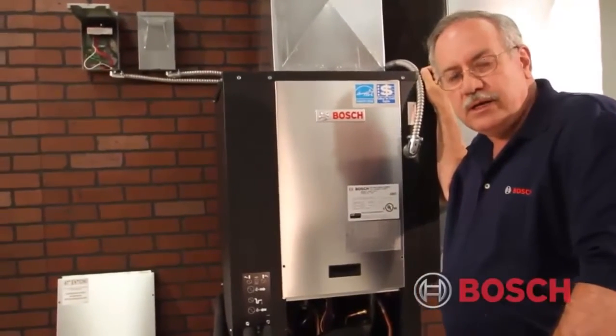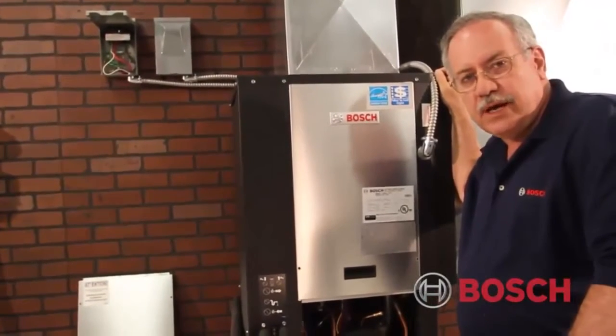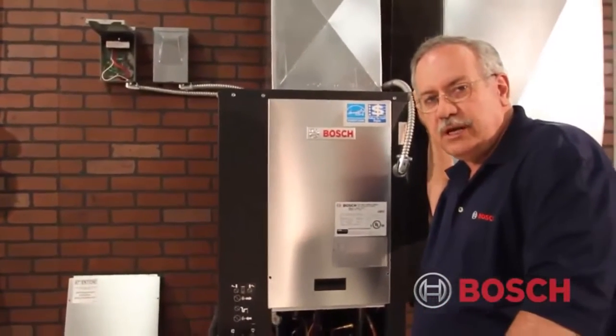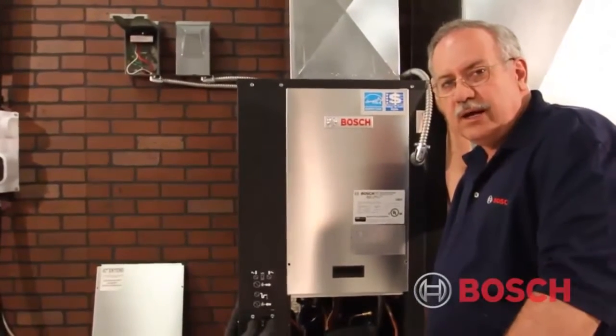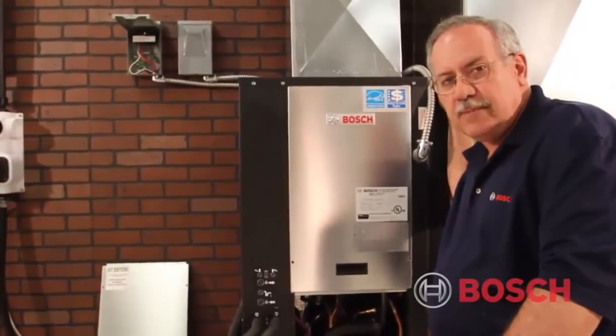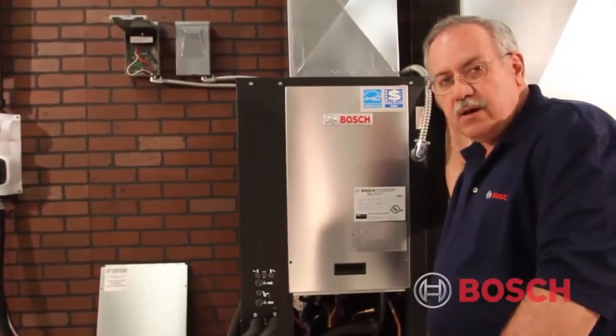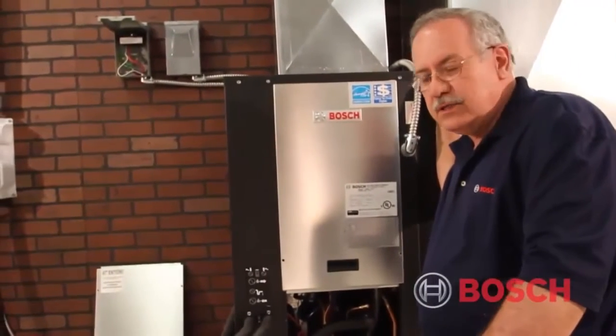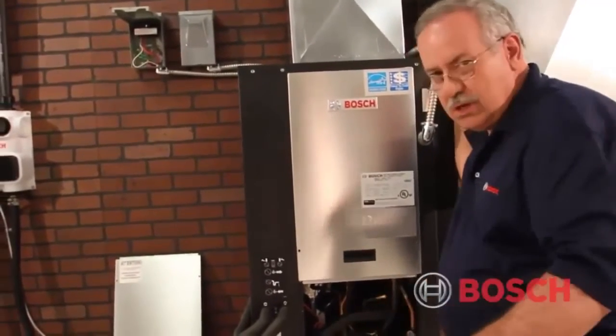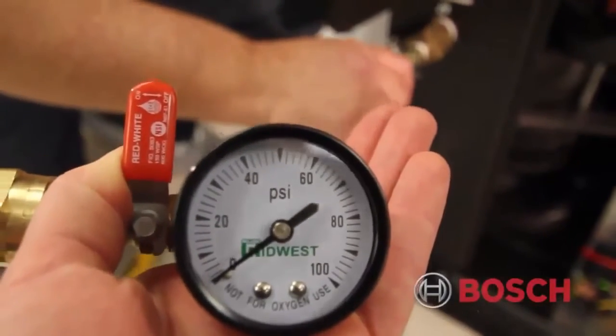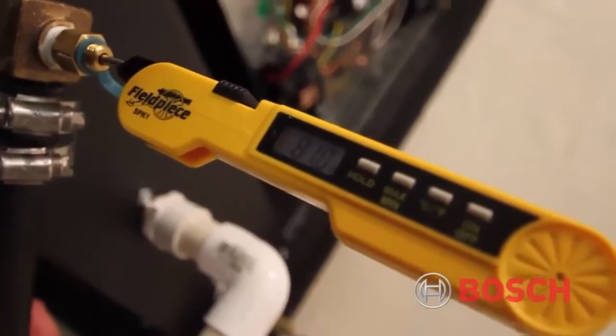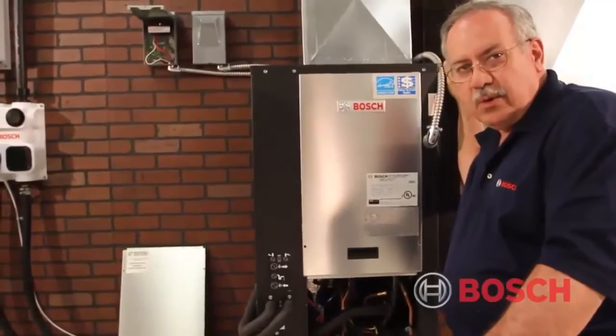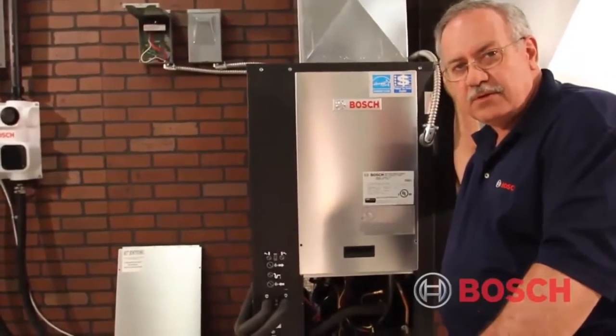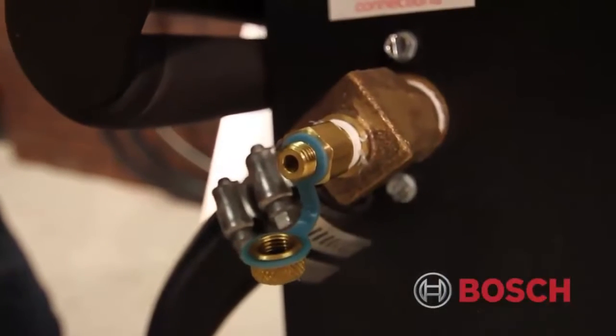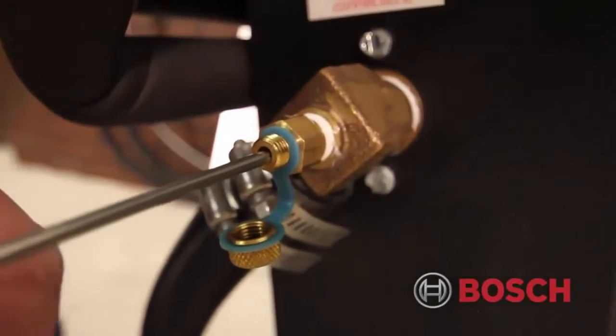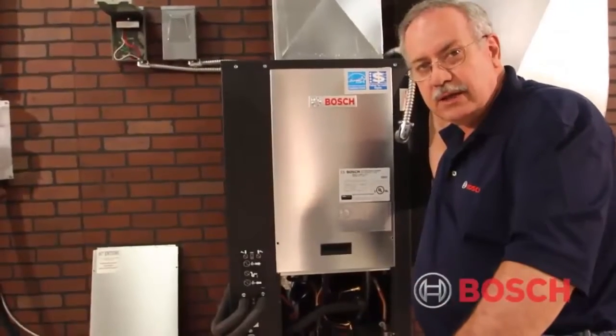The last thing we want a technician to do is to connect a set of manifold gauges for refrigerant processes to this machine. It will be the very last thing, and we try to always prohibit that as much as we can. We can check pretty much everything we need to know with the waterside diagnostics. So the process that we'll do is I will use available tools, a pressure gauge as well as a knife blade, some people call it that, thermometer, typically digital, and I'm going to go to the pressure temperature ports, commonly referred to as PT or Pete's plugs ports, that are on the entering and leaving side of the coaxial heat exchanger inside the machine. They're on the outside of it, but it's connected to the coaxial in the machine.